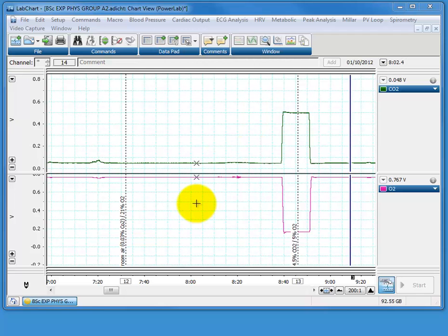where we've exchanged gases. We've got here a marker saying room air, so that's 0.03% CO2, 21% O2, or 20.9% if we're going to be precise. And then over here we've gassed the Servomex with a mixed gas of 4.5% CO2, 5% O2.